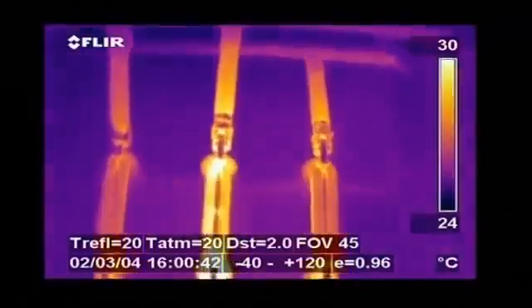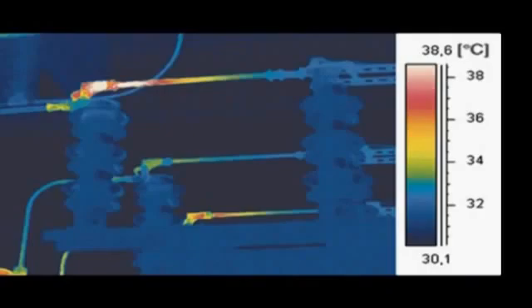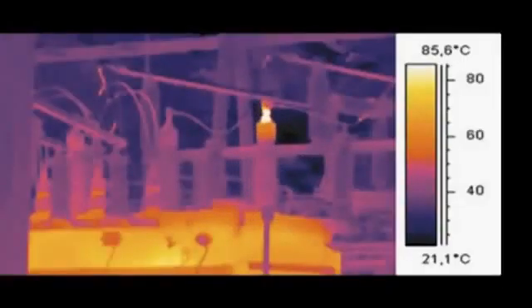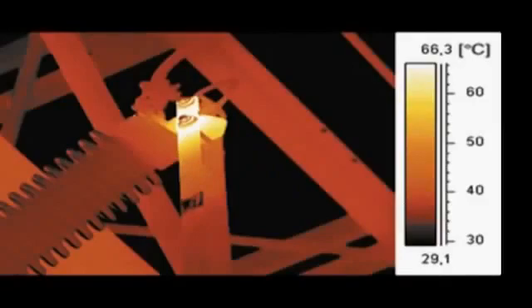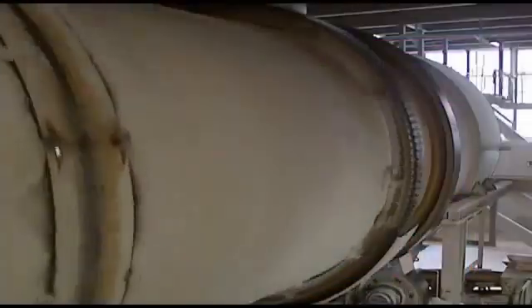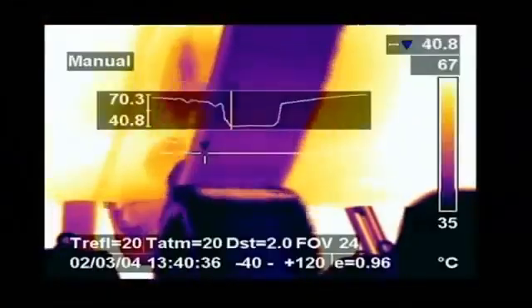Examples of failures in high-voltage installations are oxidation of high-voltage switches, overheated connections, incorrectly secured connections, insulator defects. In many industries, mechanical systems serve as the backbone of operations. Thermal data can be an invaluable source of complementary information to vibration studies in mechanical equipment monitoring. Mechanical systems will heat up if there's a misalignment at some point in the system. Thanks to features such as line profiles, you will immediately see if there's a problem.